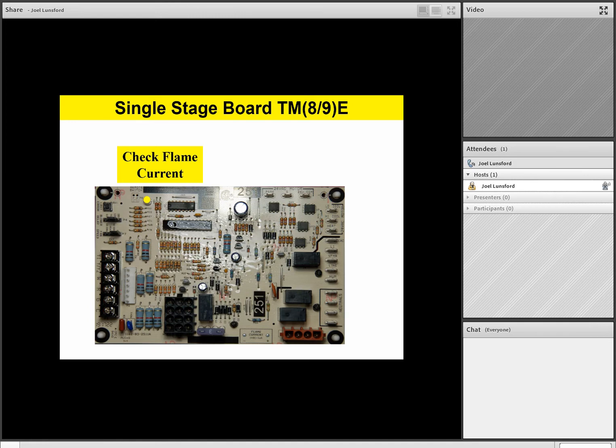Check your gas flow to make sure that the furnace is being fired properly. If you have inadequate gas or low gas pressure, you won't have proper flame, and it can affect the flame sensing. Make sure your sensor is in the proper location. Make sure that your flame sensor is not bent or moved over or shorted to ground. So make sure it's in the proper position in the actual flame itself.